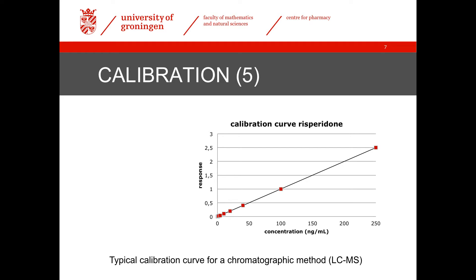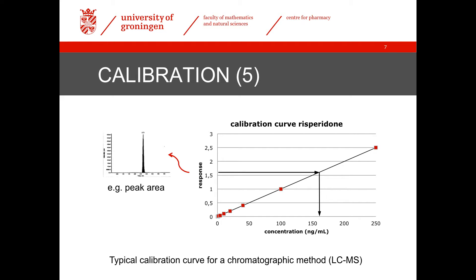The response of the calibrators is measured and plotted as a function of the concentration. For LC-MS, this typically gives a straight line. If a study sample is now measured, it will also give a response, and the concentration of this sample is determined by comparing it to the response of the calibration curve. A response can be several things, but for chromatographic methods such as LC-MS, it is usually the area or peak height that corresponds to the analyte.